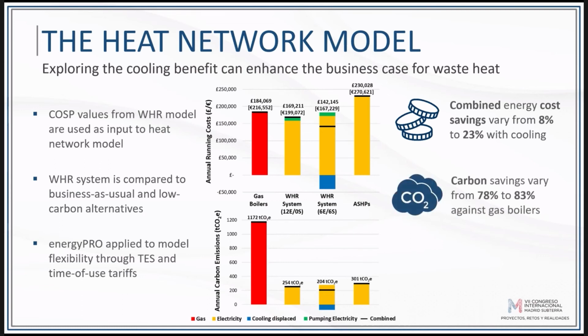In terms of carbon savings, there are additional benefits as well. It goes from 78% against gas boilers if we're only considering extract mode, up to 83%. It's not a big increase as we observed for costs, because carbon savings are mainly associated with heating—changing to the waste heat recovery system is already enough to get almost 80% of carbon savings.